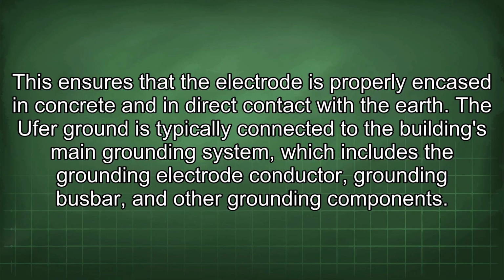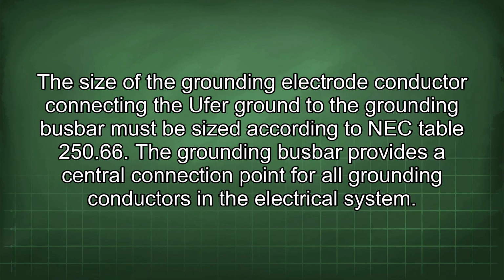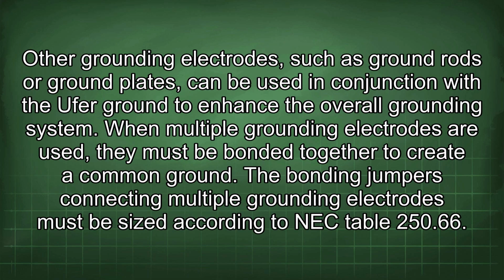The Ufer ground is typically connected to the building's main grounding system, which includes the grounding electrode conductor, grounding busbar, and other grounding components. The size of the grounding electrode conductor connecting the Ufer ground to the grounding busbar must be sized according to NEC Table 250.66. The grounding busbar provides a central connection point for all grounding conductors in the electrical system. Other grounding electrodes, such as ground rods or ground plates, can be used in conjunction with the Ufer ground to enhance the overall grounding system.